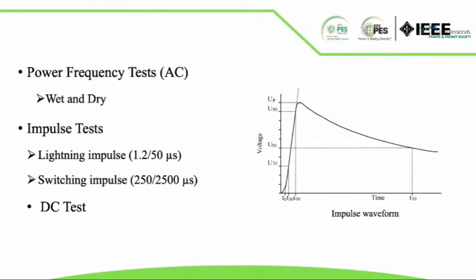In order to check the withstand capability of the equipment, the apparatus is subjected to a 1 minute test under 50 Hz frequency, and its test voltage is set at a voltage greater than the expected working voltage in order to simulate a stress-like situation likely to be encountered by the equipment during years of service. For indoor installation, the tests are carried out under dry conditions, and for outdoor installation, the tests are carried out under both wet and dry conditions in order to simulate rain-like conditions.